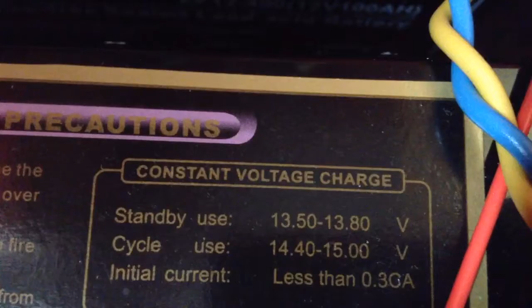The initial current should be less than 0.3 C amps. In this case, C is 100 amp hours, so 0.3 C is about 30 amps. So the charging current should not exceed 30 amps per battery. In my case, that's not a problem, as I could only produce 30 amps maximum between the 3 batteries, so that's only 10 amps per battery.